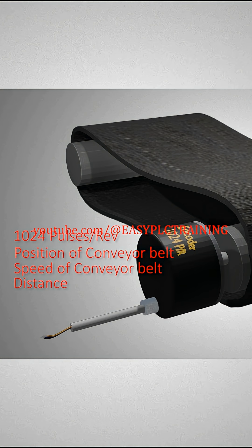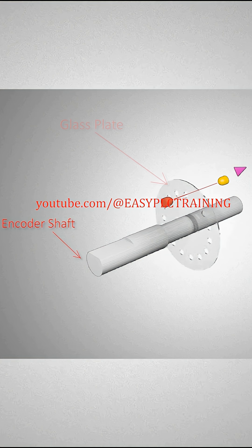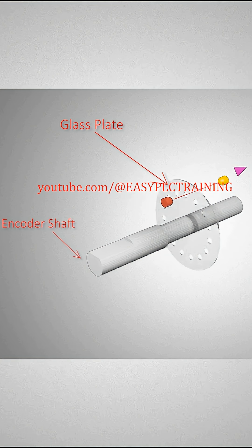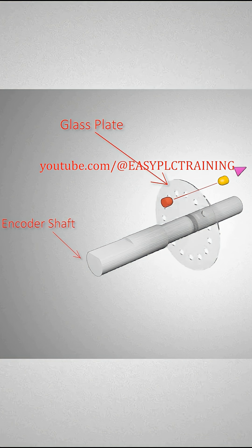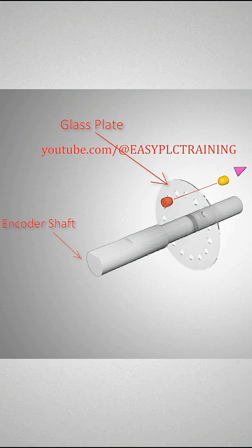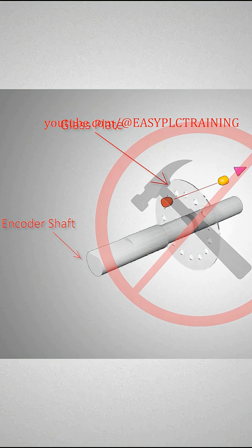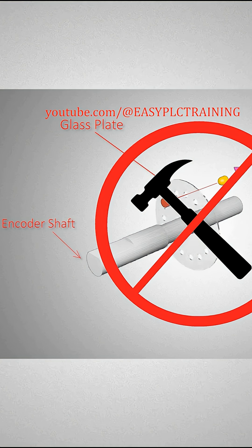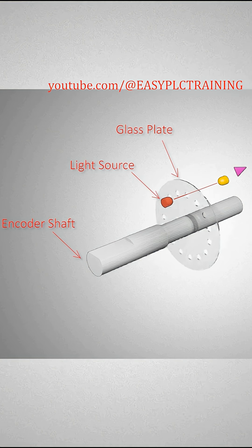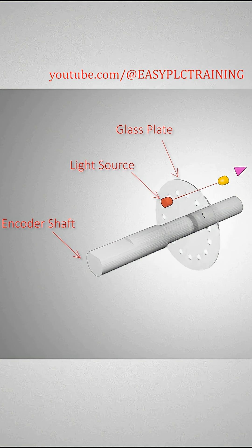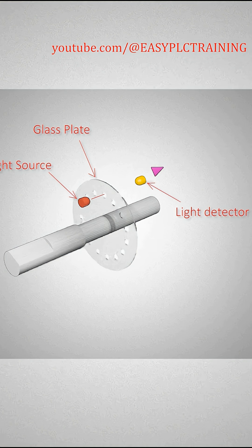If we remove the back cover of the encoder, you will find a glass plate connected to the shaft. This glass plate has a circular array of small holes on it. This glass plate is very fragile. If you ever need to remove the encoder from the shaft of a motor, never use a hammer or force to remove it, as it can damage the glass plate.